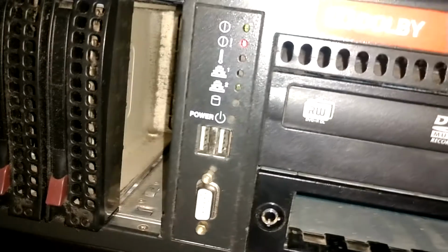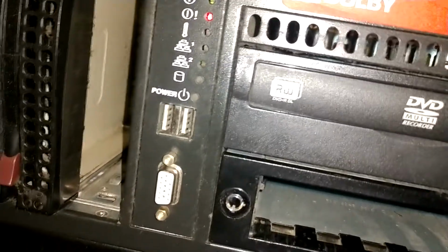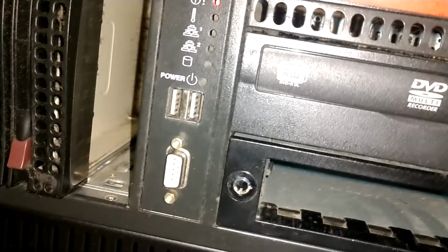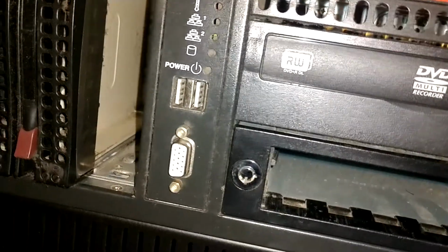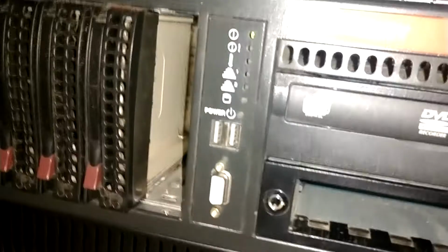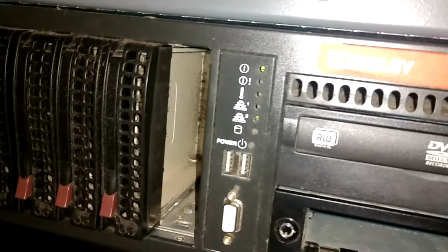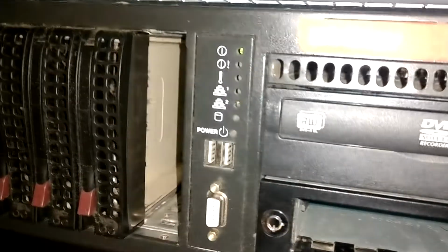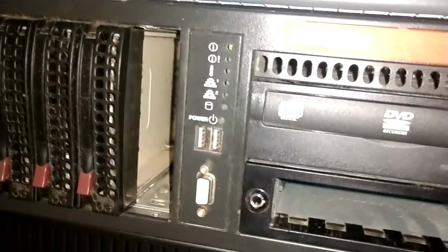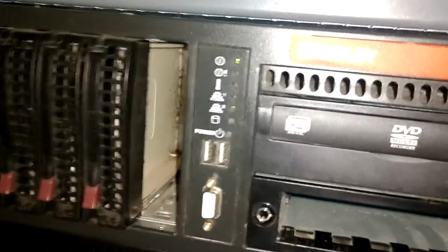Now if I flip the breaker off, that light comes back on. So there's 2 separate power sources, but in either case, the server is still on and running. Flip the breaker back on, that light goes out. The only way for the server to go out is to lose both of its power supplies, both the primary supply and the battery backup.